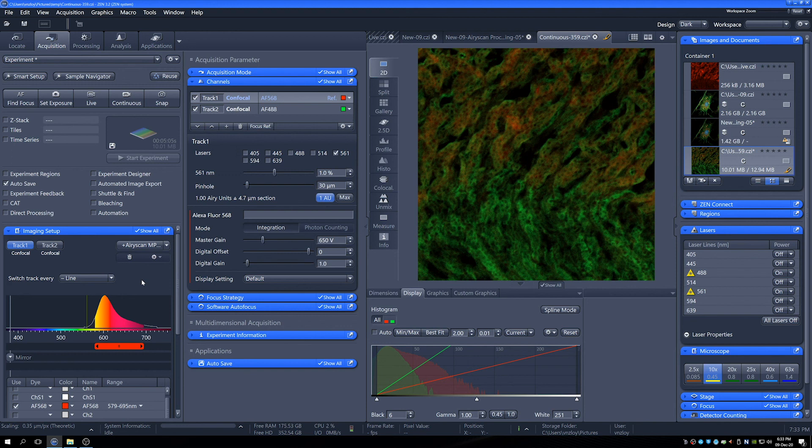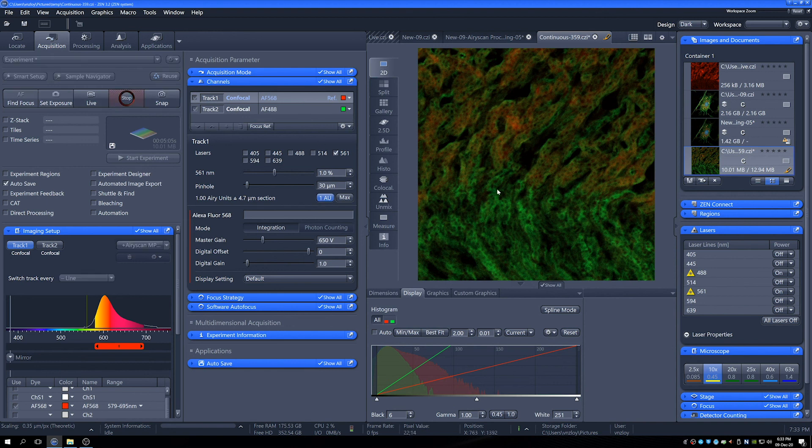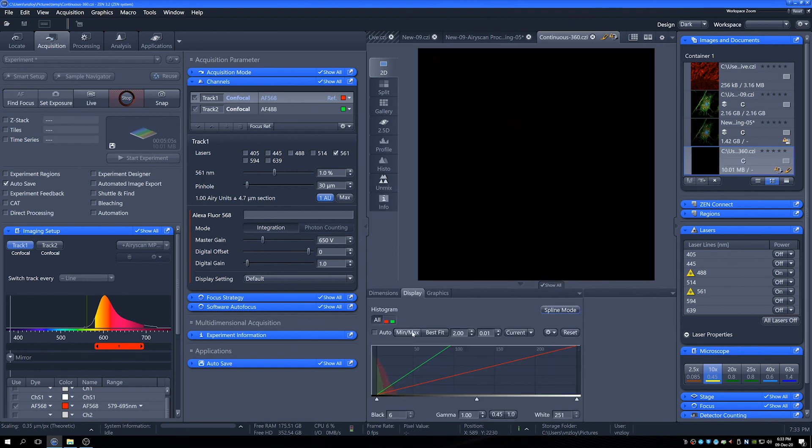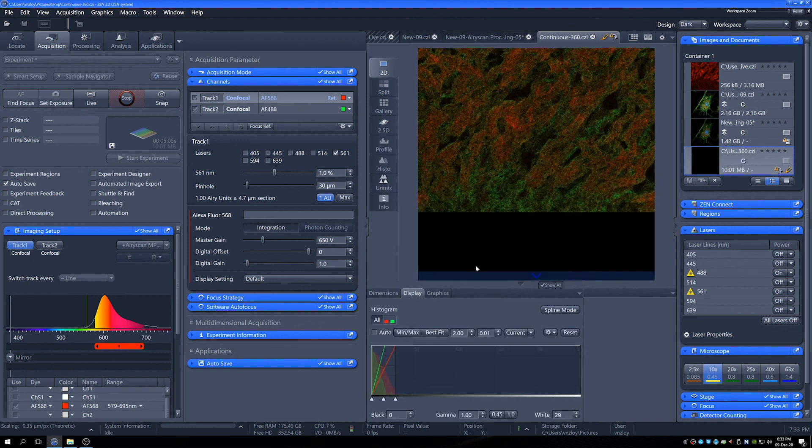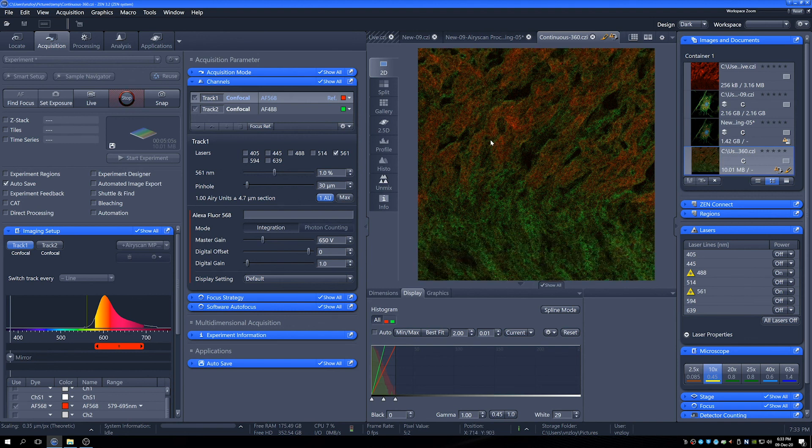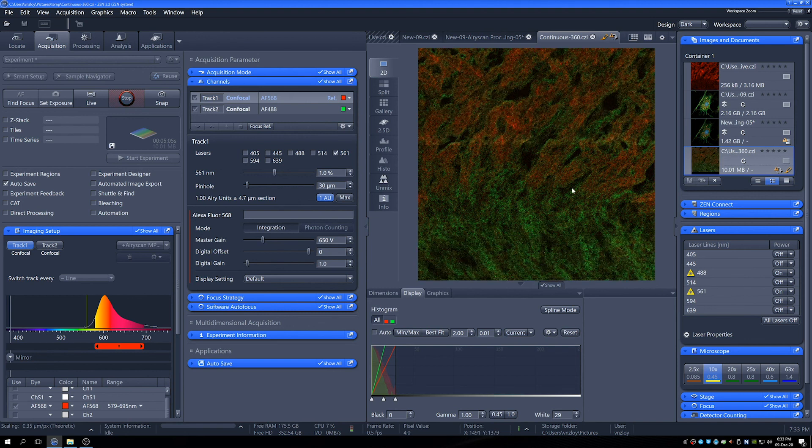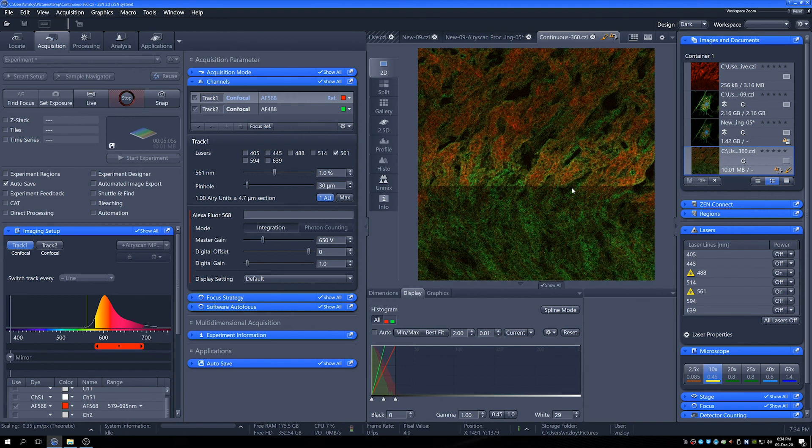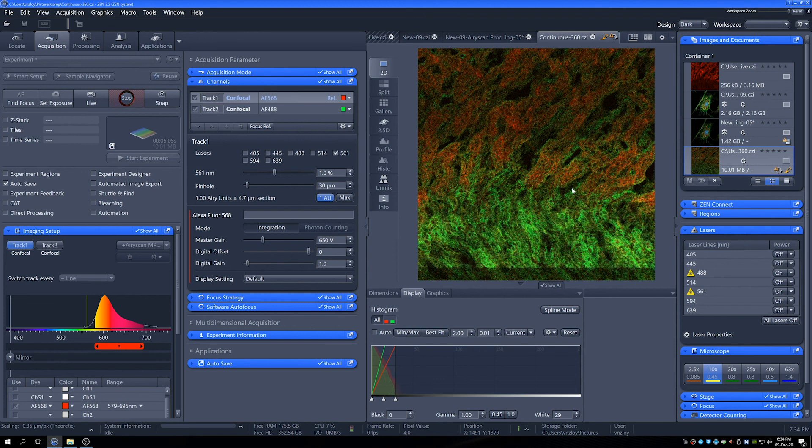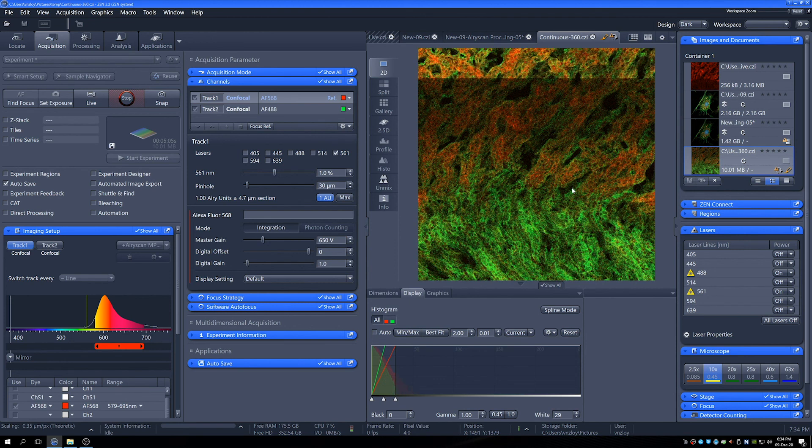Then you would normally set 1 AU on the reddest dye that you're using. Now if we have a little look at continuous, we'll probably see a big change in the amount of signal that we're collecting, just because now we've actually got a pinhole present. But we'll see now that the detail of the actual sample has also improved quite markedly as well. So this is the kind of thing we can expect.